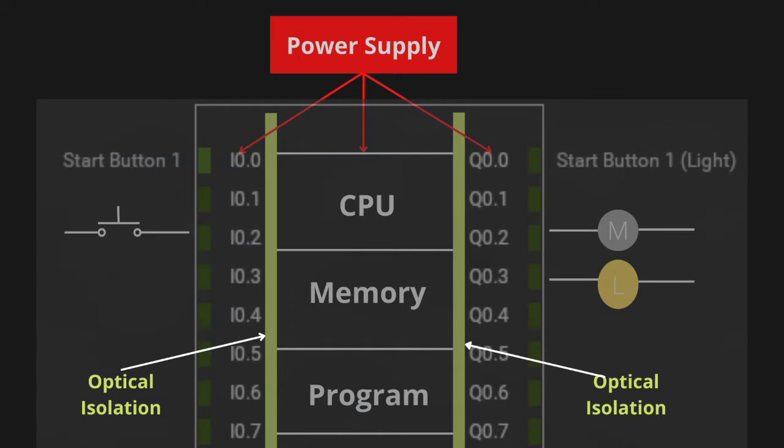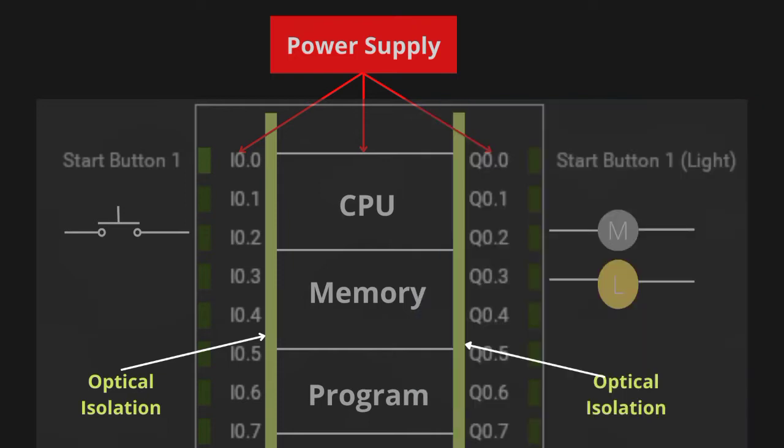Always refer to the manual before powering. Some PLCs can be directly connected to AC mains, as they have a switch mode power supply built inside, and for others, we need a 12 or 24 volt DC external power supply. The power supply is used to power PLC and the IO modules.